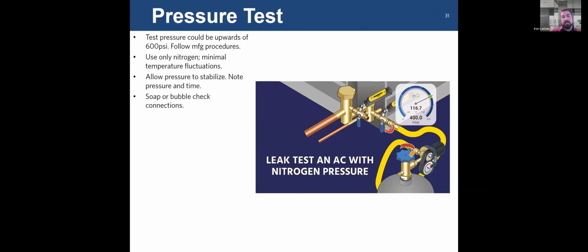Sometimes people do put trace gas in here, and they'll pressurize with just a little bit of refrigerant and nitrogen, and then actually use a refrigerant detector at all your joints. You can also soap or bubble check all your joints. I would typically do this: I would put my system on the pressure test, make sure everything's stable, make sure the gauge isn't moving at all, that I've got no major leaks, and then I would go and soap check all the connections. Even sitting here for an hour, sometimes you'd have a leak so minute, so tiny that you won't see it on the gauge, but you will see little tiny bubbles form. It'll give you the chance to reset that connection, particularly if it's a flare connection, and then redo the test.